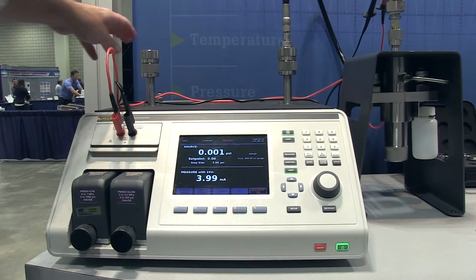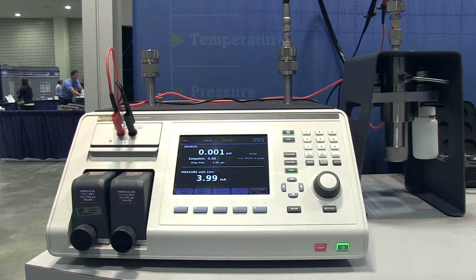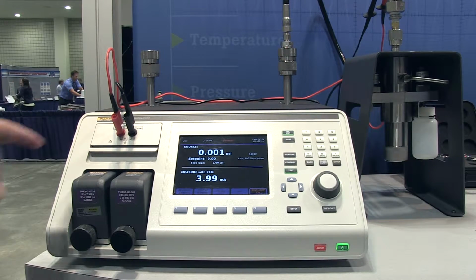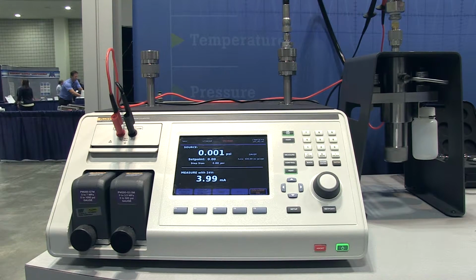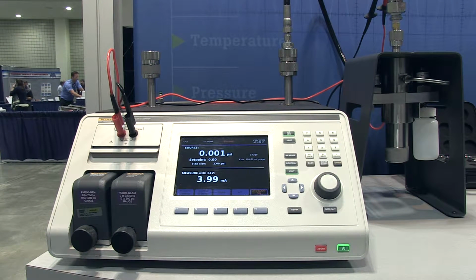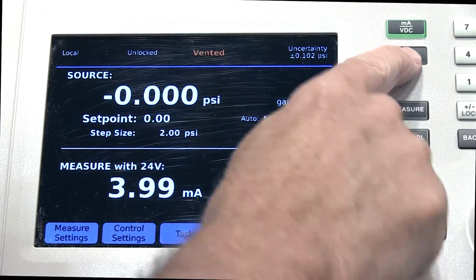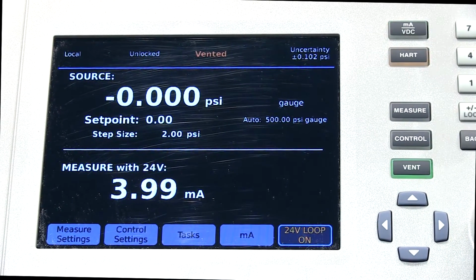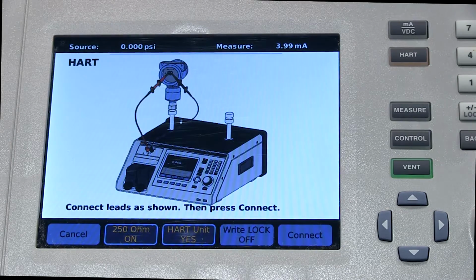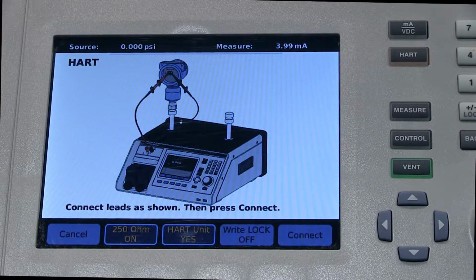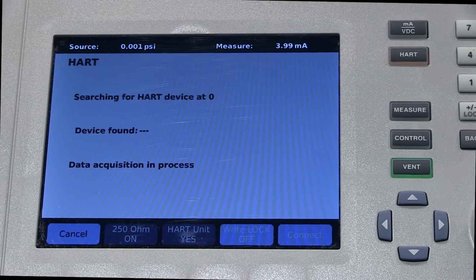It also includes 2 test ports on the top for devices that you want to calibrate, so you can even test 2 at a time. And it includes a new electrical measurement module for doing 4 to 20 milliamps, 0 to 30 volts, and HART communication. So there's a dedicated button over here for connecting with HART instruments. You hit it and it goes out on the loop and tries to communicate with any devices. After it connects, it will allow you to change parameters, make trims.